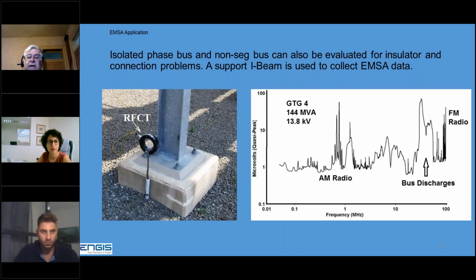Isolated phase bus and non-segregated bus are easily tested. We've been doing this for a very long time. We found several problems. There is a lot of safety grounds involved in the system. So what we do, here's an I-beam that supports the bus, which is up here, and that safety ground goes to the ground mat. We put the current probe around one of those safety grounds. So on GT4, this is what we got. Very strong radio signals and a lot of discharges here on the higher frequencies. This is where isolated phase bus noise shows up, right around the FM radio stations. It's not too bad because it's not much stronger than the FM radio or the AM radio, but there are some discharges in the bus.